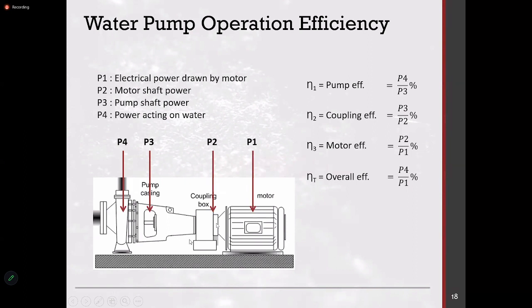Most of the time you align them properly, because misalignment will be a big problem. You use a laser beam to actually align them correctly, the coupling and the shaft, because if they are misaligned, then your motor power consumption will increase, and your pumping output will reduce. So all these will come into play. So the overall efficiency is this pump output over the power consumed by the motor. Okay. So these are their individual efficiencies. Okay.